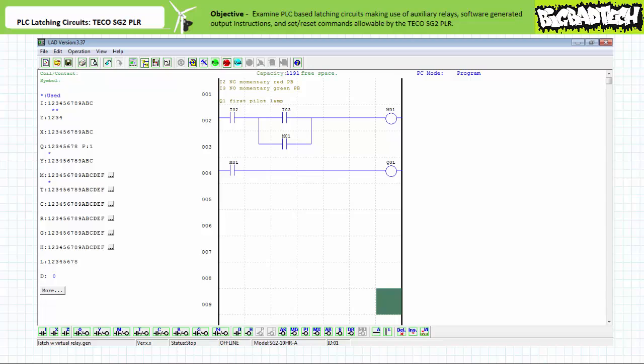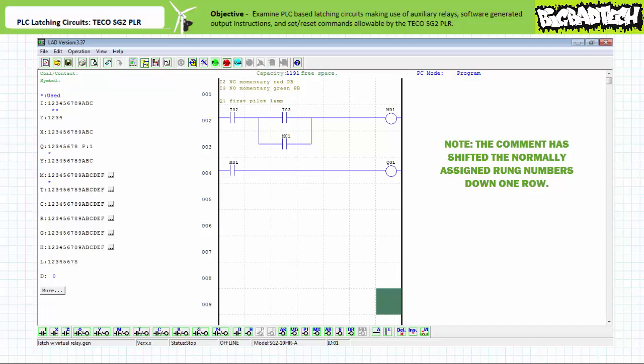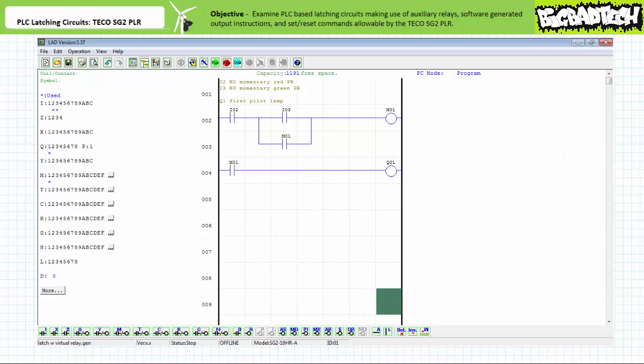Note the comment section indicates we're using the normally closed momentary contact red pushbutton for input 2, the normally open momentary contact green pushbutton for input 3, and the first pilot lamp for output Q1. Rung 1 is a series configuration of a make instruction examining input I2 and another make instruction examining input I3, controlling the coil of non-retentive auxiliary relay M1. Rung 2 is a make instruction examining M1 in parallel with the make instruction examining input I3 in rung 1. Rung 3 is a make instruction also examining M1 in series with output Q1. One can see how the programmed instructions closely mimic a three-wire holding circuit as implemented in traditional hardwired relay-based ladder logic.